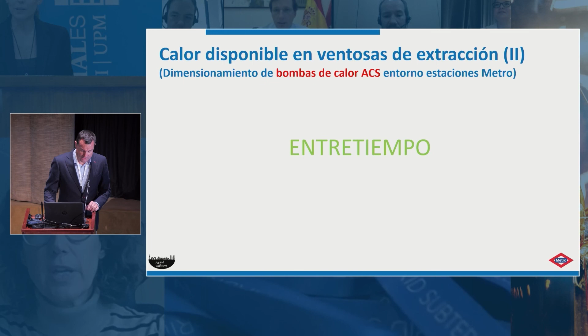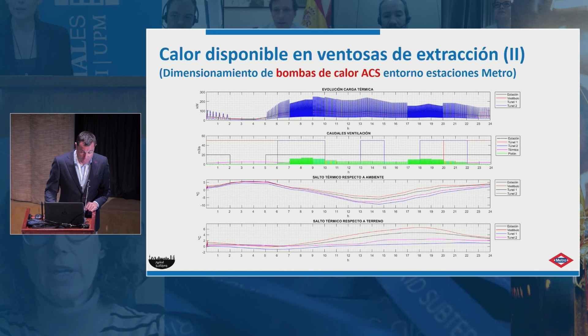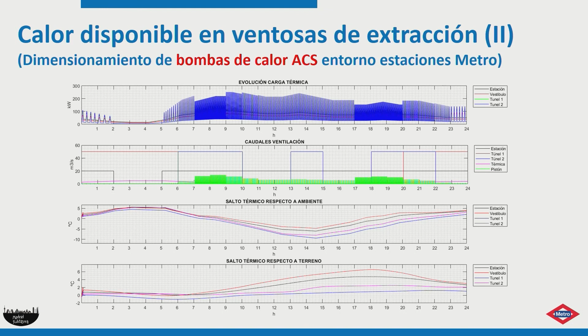In a spring or fall day, the outside temperature is going to be higher than the temperature of the terrain, and that's where the interaction between the different parameters becomes increasingly more important. Heat transferred to the soil is going to be more dominant, and our heat collection is going to be affected. Here we see we're injecting heat when the fans operate, and this is magnified in the case of a summer day.